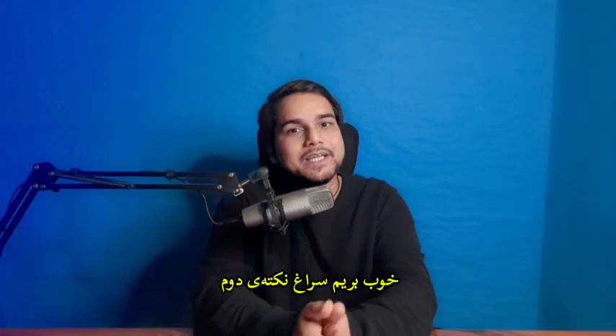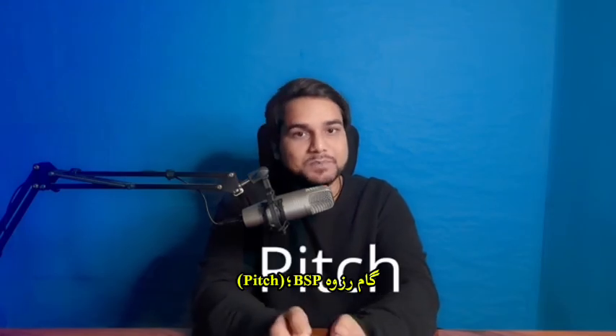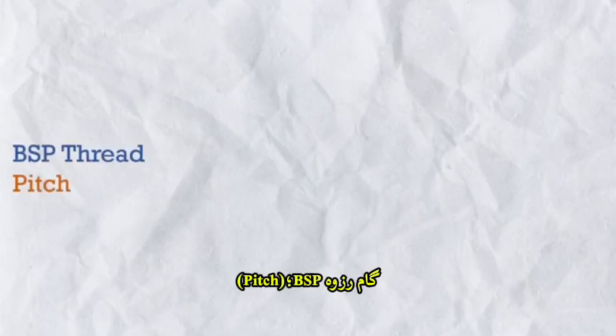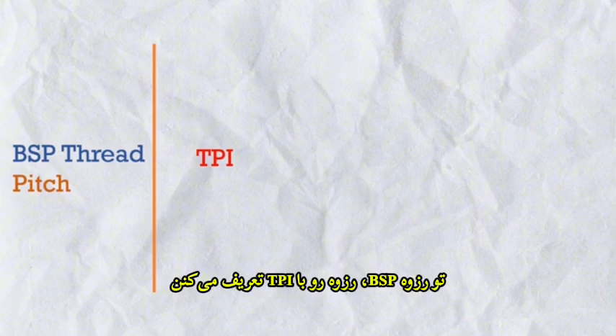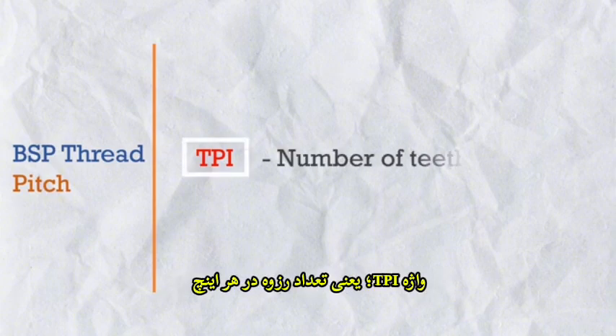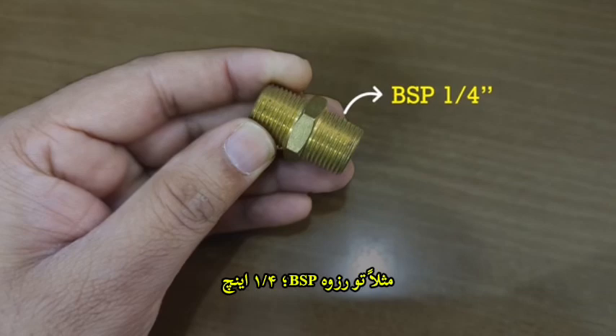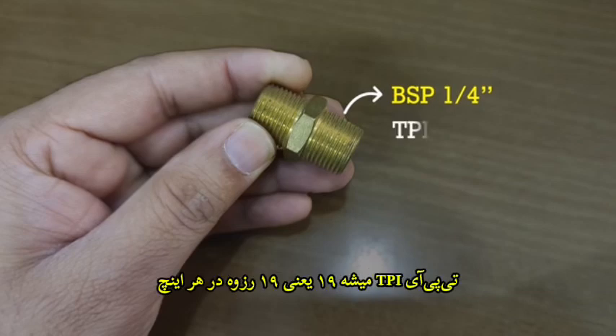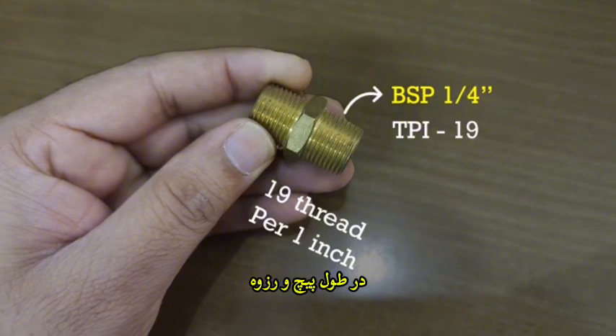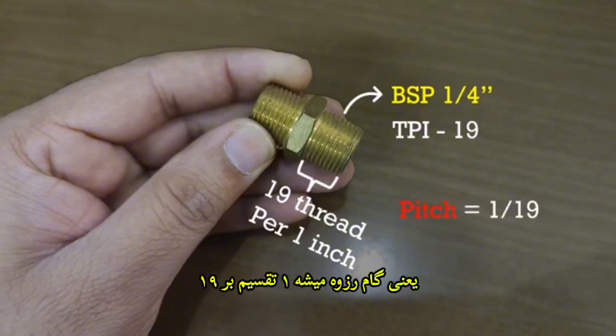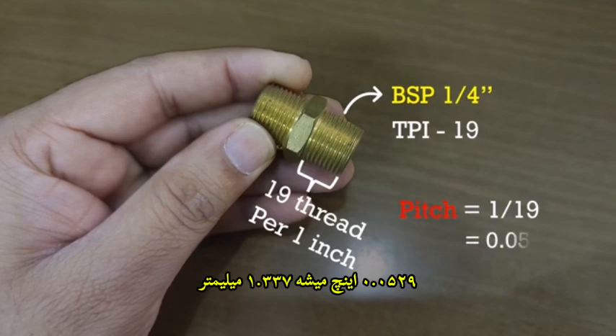So let's move to the second thing, the pitch of BSP thread. In BSP thread, we define the thread in TPI. TPI means number of threads per inch. For example, in 1/4 inch BSP thread, TPI is 19. Means 19 threads per inch of length of the thread. Means pitch equal to 1/19, 0.0529 inches, means 1.337 mm.